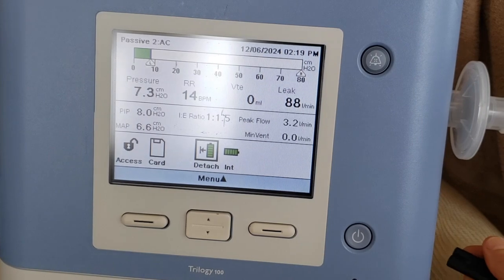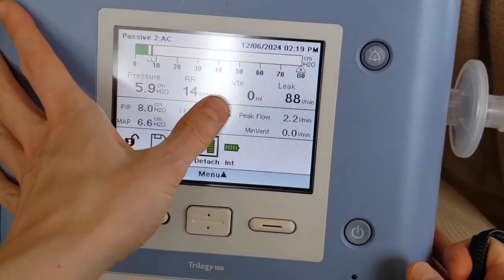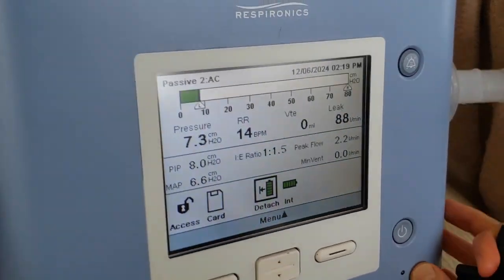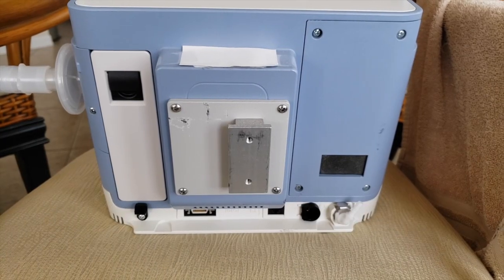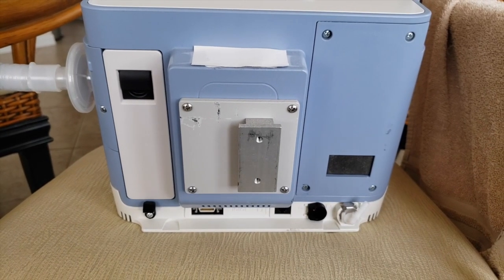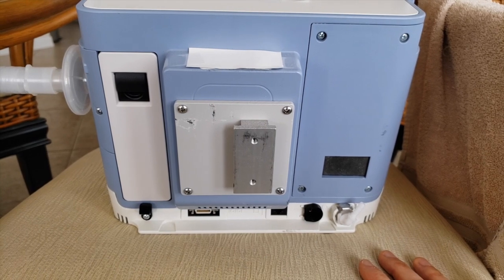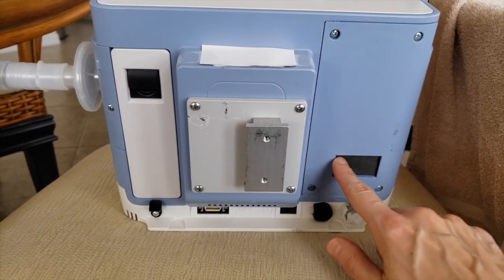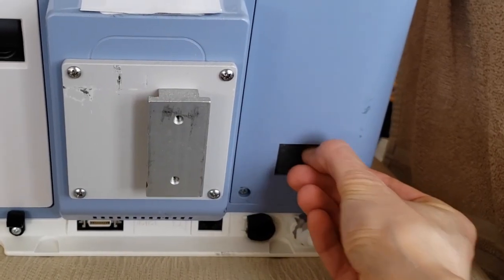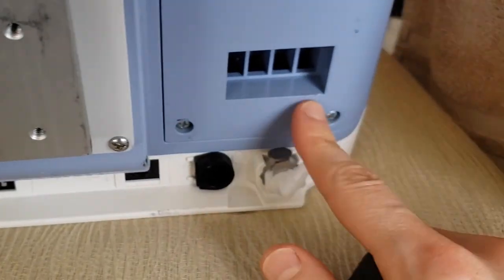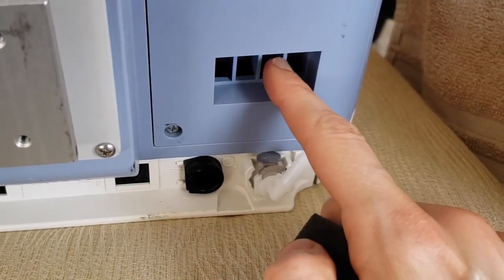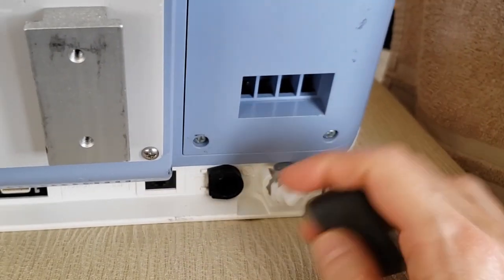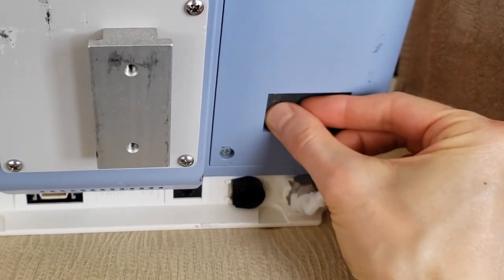And there you go, it is all back to normal. So let's continue on, flipping this over to the back side. Okay, this is the back of the machine. It's pretty simple. First of all, the way the ventilator breathes in is through this intake right here. There is a filter over it, but if you take that off, this just goes directly into the machine. It takes room air and then it pressurizes it and gives me a breath in.